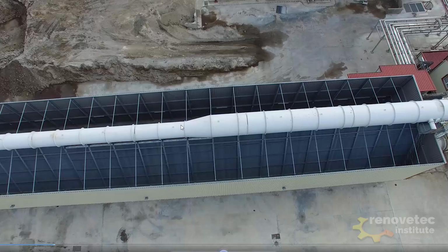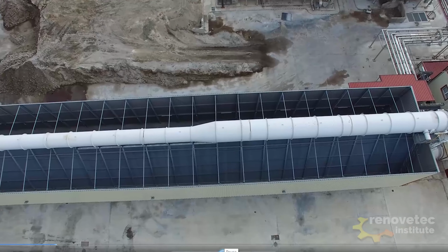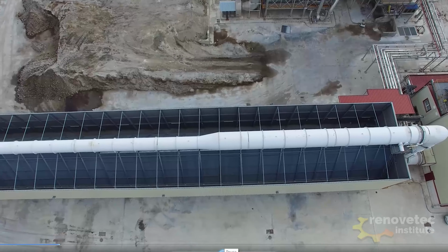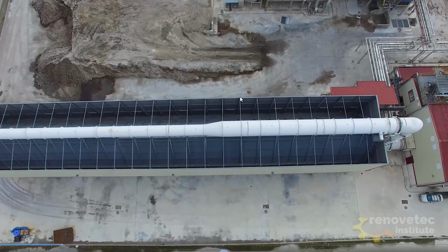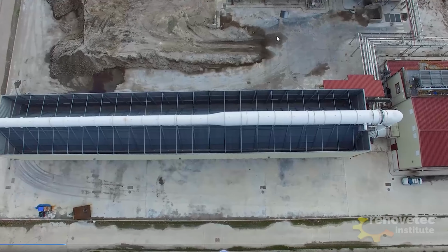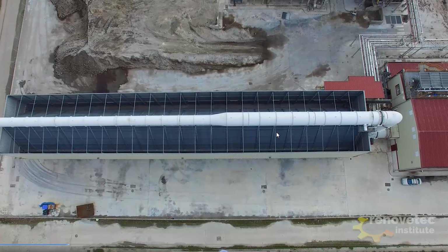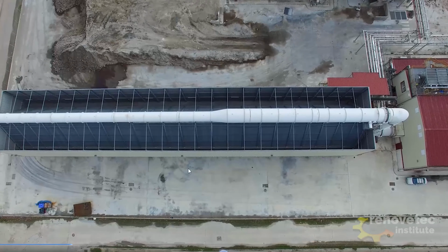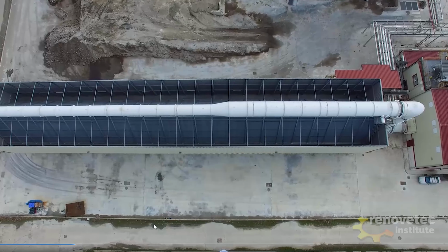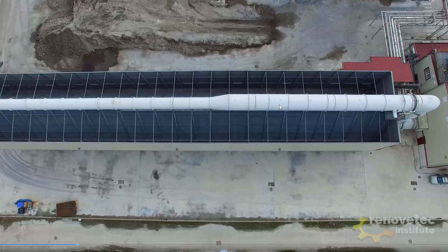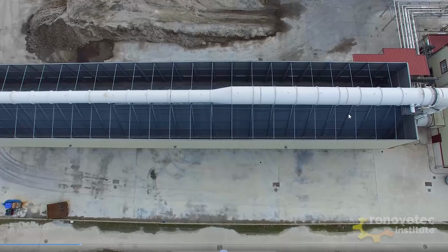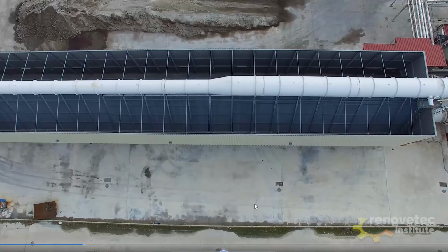It is more common to have a cooling tower than an aero condenser, but in this case there is no water near the plant, and they prefer to use an aero condenser. The aero condenser is very, very high because the power of the plant is around 15 megawatts. See the size of the aero condenser. There are at least 4 sections with 4 ventilators, very big ventilators.